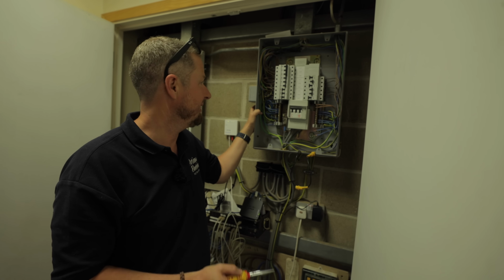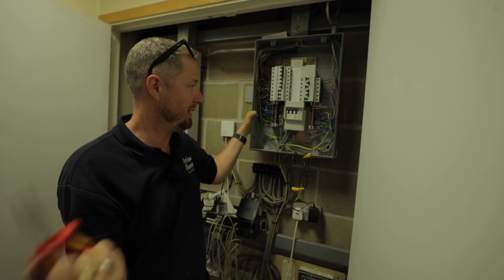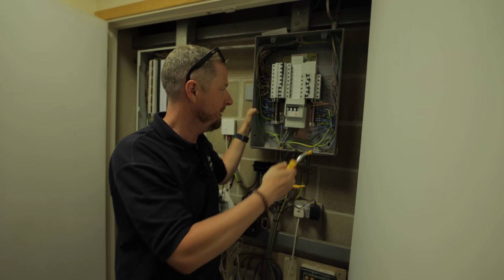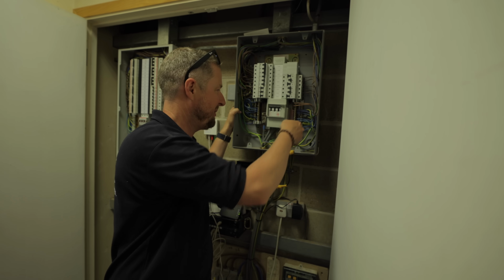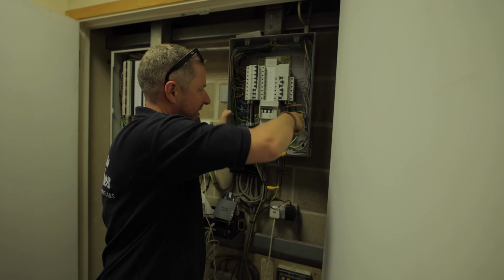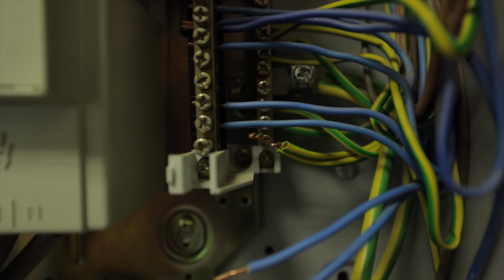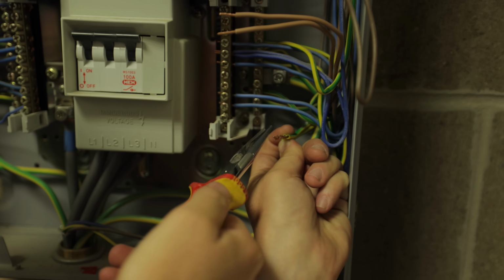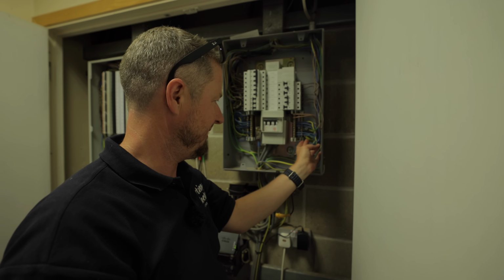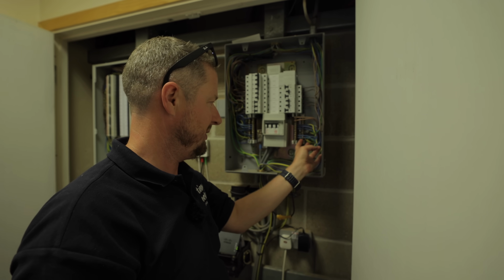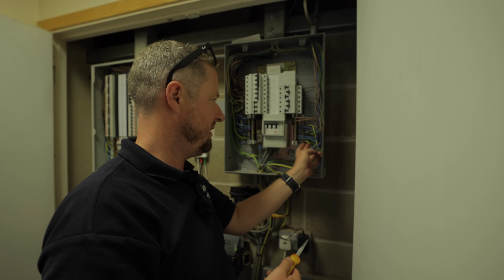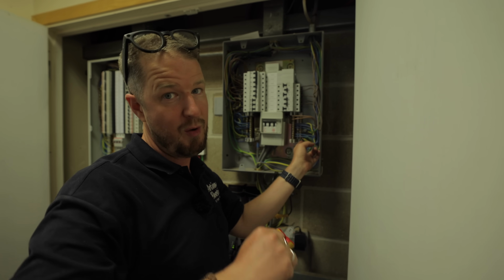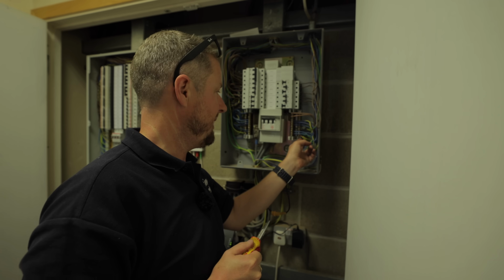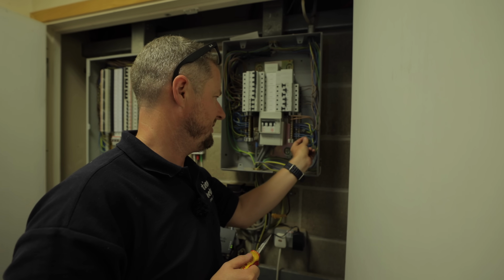We don't have many ring circuits here, but there's one I want to test, so I've been explaining to Jacob how it works. I've just come across one of my biggest bugbears: they've twisted the earth wires together, which means you have to untwist them to separate them, and you often end up snapping them off because they've been twisted so tightly. Really, you should never twist wires together like this for a ring circuit. You should put them in separately, maybe double them over if you're worried about screwing through and damaging the copper, but twisting them together is just a bad idea.